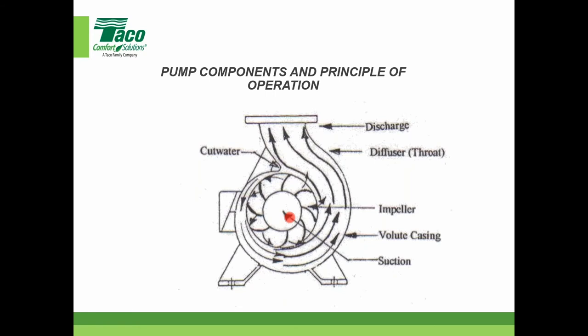We test them on a periodic basis, but we don't have to flow test every pump unless someone wants a certified one. That's another whole discussion you could have with your rep. But we do pressure test them to make sure there's no leaks and there's no porosity in the casings. Nowadays, the casings really rarely leak, and there's very little porosity in it. The manufacturers and the folks that do the casings, castings, do a pretty good job now. The other term that's, you know, important to at least realize is cut water, and that's the dimension between the maximum impeller and the pump where the water flows around or distributes back into the diffuser on its way out.